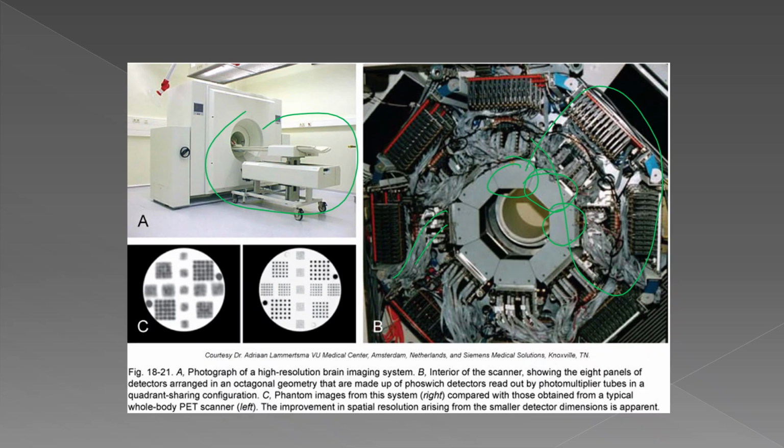The other thing that I just thought of is that I want you guys to know, remember in gamma camera imaging, we have a pulse height analysis and you have a window and a photo peak and things have to be within like plus or minus 10% of the photo peak. Well, with the PET scanner, you still have a pulse height analyzer and you still have a window.